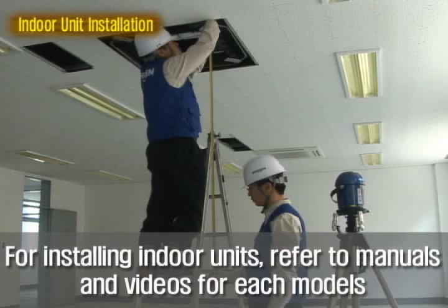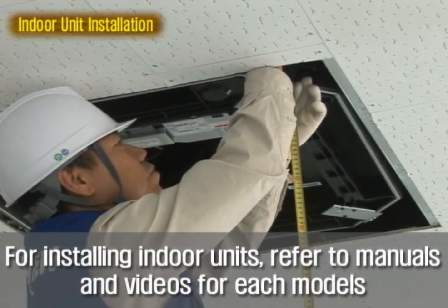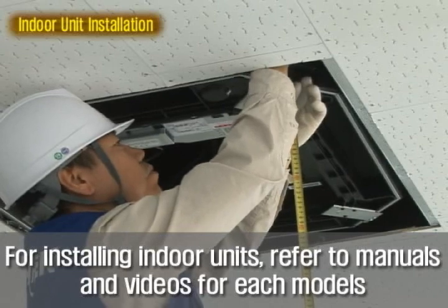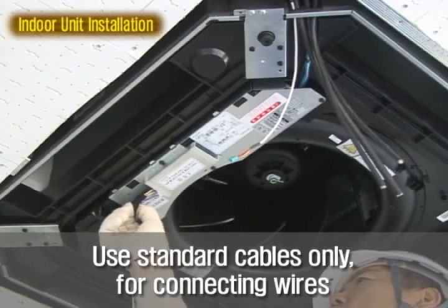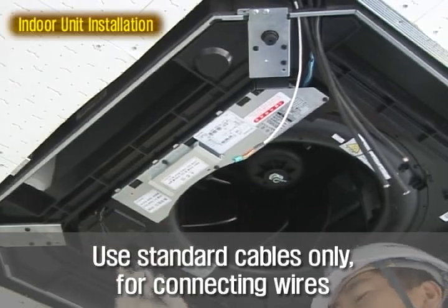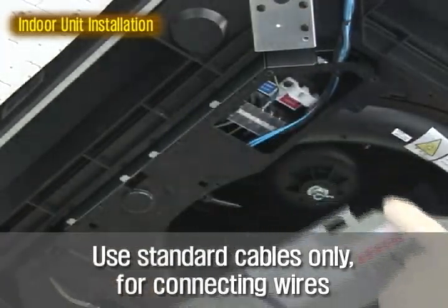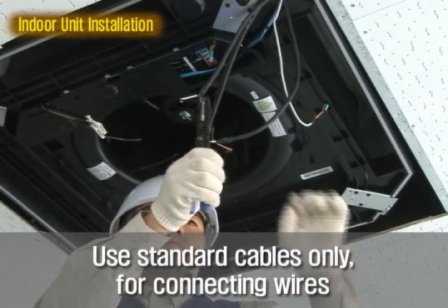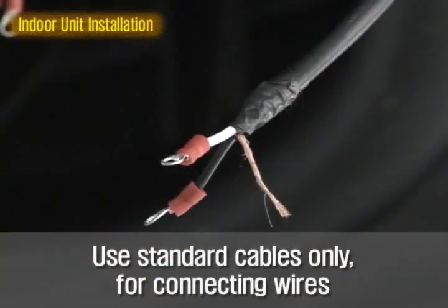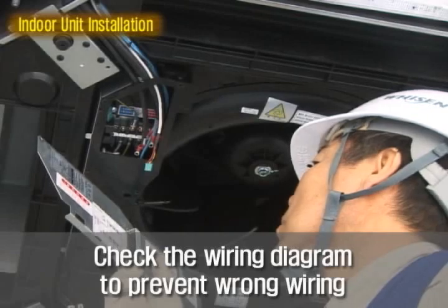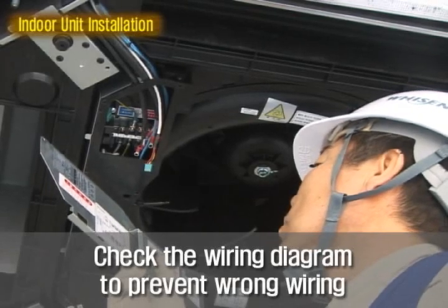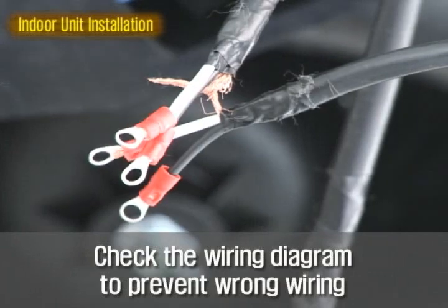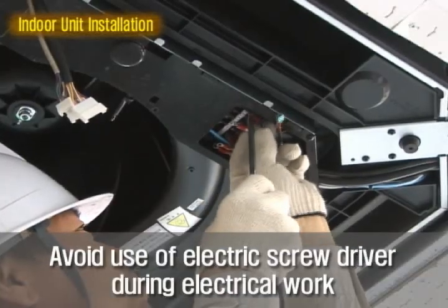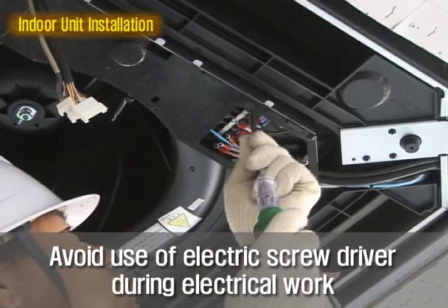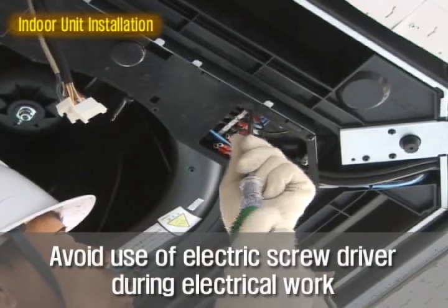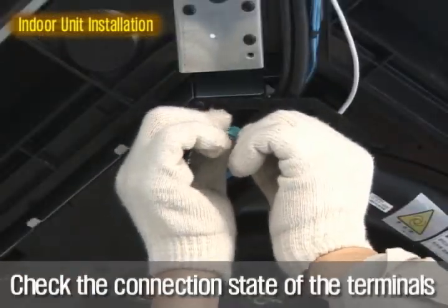For installing indoor units, please refer the manuals and videos for each models except the wiring. For the wiring work, refer following. Disassemble control cover and cord clamp for cable connection. Terminal type connection is used to prevent the contact resistance defect in the wire connection. To avoid a wrong wiring, check the diagram first. Connect indoor power line and communication cables. For grounding this communication cables from each indoor unit, peel out cables, combine them, and connect using terminal.